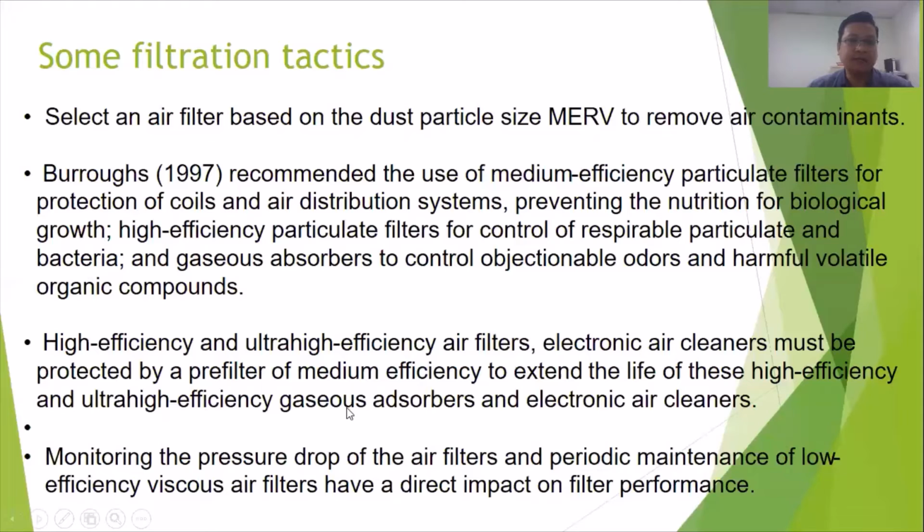High efficiency and ultra efficiency air filter and electronic air cleaner must be protected by a pre-filter of medium efficiency to extend the life of the high efficiency and ultra high efficiency, gaseous adsorber, and electronic air cleaner. So in this classification of air filter, high and ultra high should be covered or protected by a pre-filter, because high efficiency and ultra high efficiency is very expensive. So before that, we cover or protect it, then it is easy to clean the air filter itself.